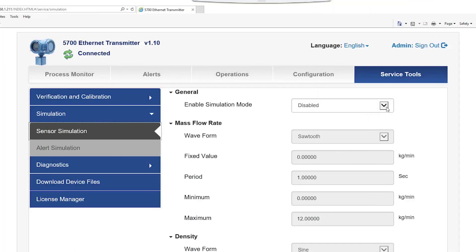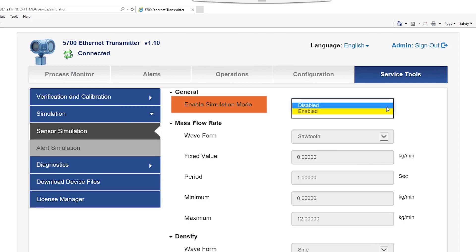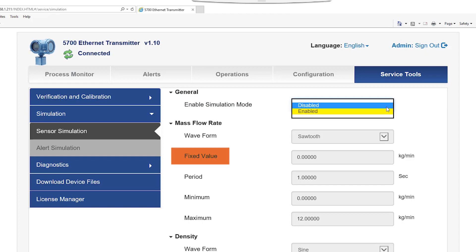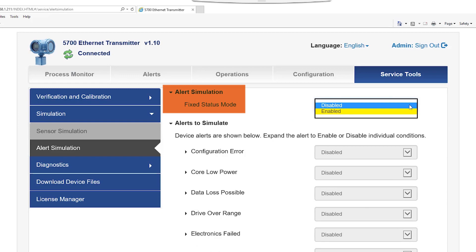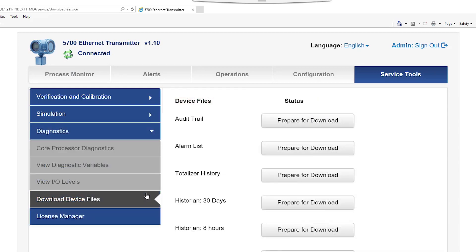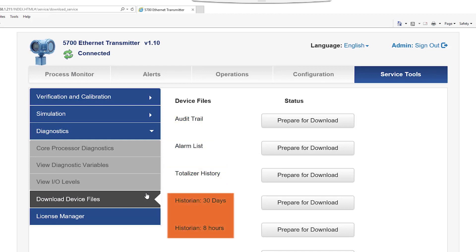The sensor and alert simulation menus allow the user to enable simulation mode if necessary, to send a fixed value or waveform to communicate to the user's control system, and simulate alerts for testing or troubleshooting purposes. The download device files menu allows the user to access the data stored in the transmitter: audit trail, alarms list, totalizer history, and data historian files are a highlighted sample of the extensive information that can be accessed from the 5700 Ethernet transmitter.